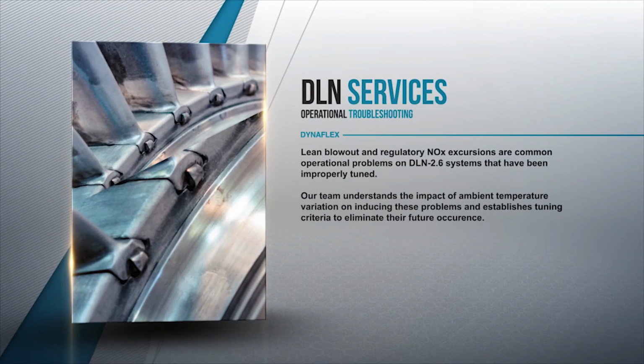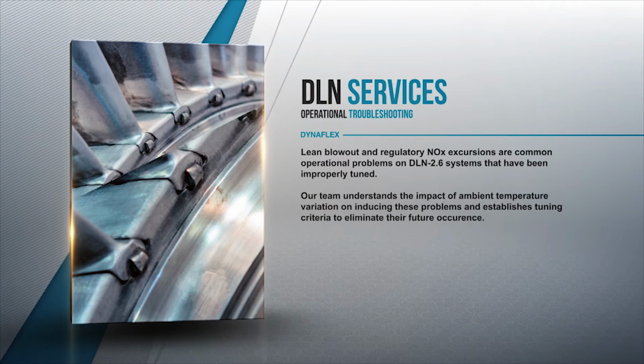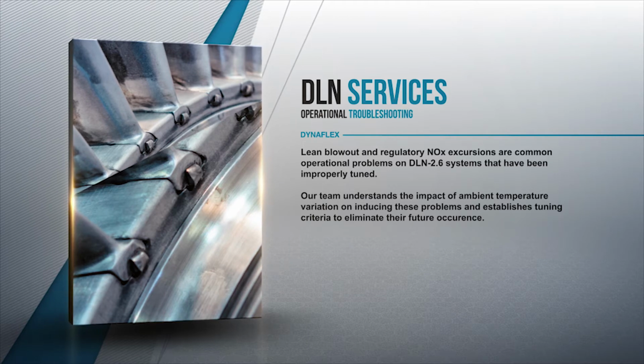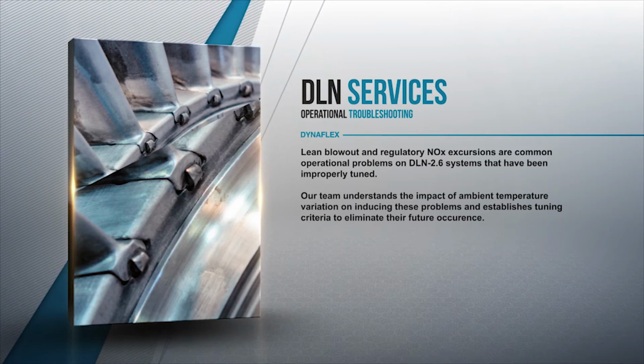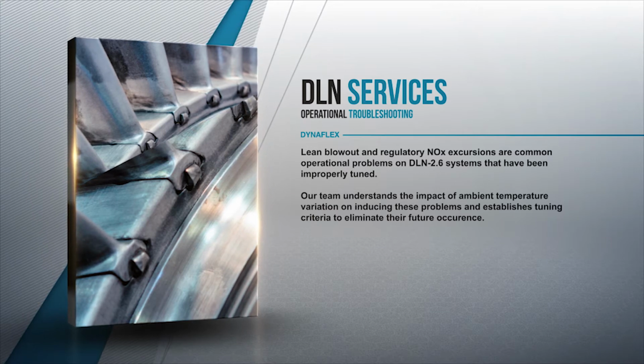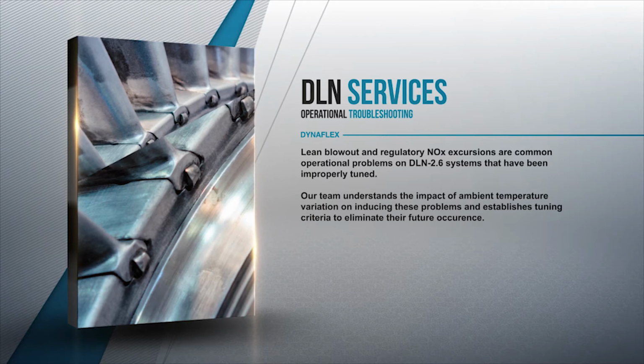Lean blowout and regulatory NOx excursions are common operational problems on DLN 2.6 systems that have been improperly tuned. Our team understands the impact of ambient temperature variation on inducing these problems and establishes tuning criteria to eliminate their future occurrence.